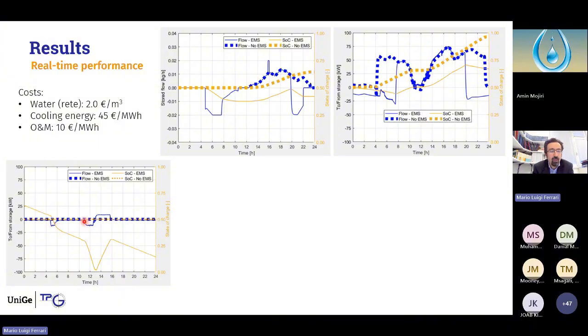However, we have a significant decrease of the state of charge due to heat loss, because the circuit maintained the pumps active, and we had about 1 kilowatt of discharging due to not perfect thermal losses. This generated a large decrease in comparison with the no EMS case, and the state of charge decreased to lower than 10%. For this reason, the heat pump has been maintained active for more time to recharge the system.